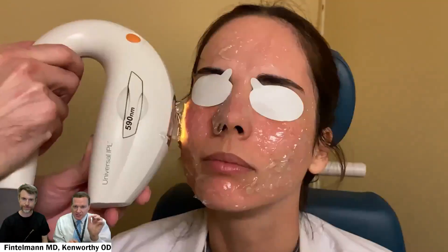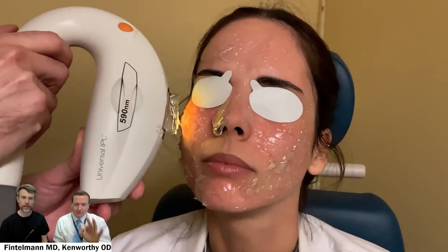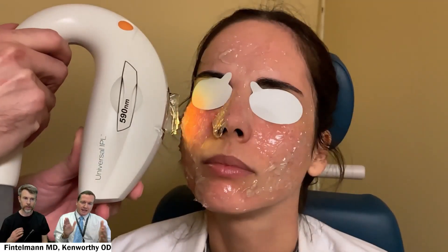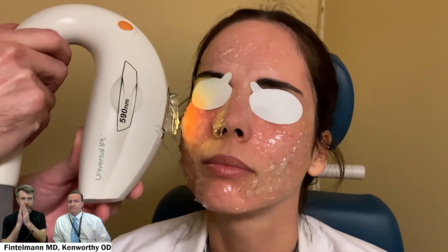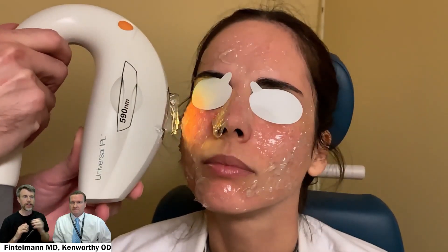This is slow motion just showing that triple flash — every time the button is pressed, it's actually three flashes in one. As was mentioned earlier, the delay in timing between the flashes will differ based on the type of treatment. The more you can spread out the energy with longer pauses, the less intense it is. The dry eye treatment has longer pauses, while the rosacea treatment pulses are very, very close together.